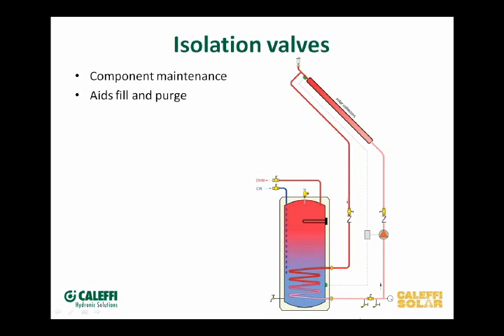Isolation valves: there's going to come a point where you want to work on something — the pump might go bad, or you might have a leak and need to change the tank. It's nice to have isolation on both sides so you can shut off and service any component. With the fill and purge valve, you get double duty — isolation close to the pump. The pump can be serviced with only a small loss of fluid. Isolation valves should also be rated for high temperature.